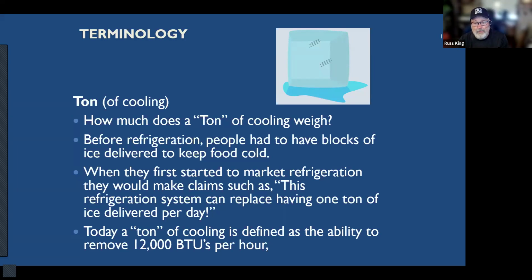All right, so 12,000 BTUs, 12,000 kitchen matches per hour, is its capacity to extract. So a 1 ton is 12,000, a 2 ton is 24,000, a 3 ton is 36,000 BTUs per hour. So when the manufacturers design an air conditioner, they shoot for one of those increments. They've designed enough of them that they know how big to make things for it to be right about 12,000 or 24,000 BTUs per hour. But then they send it off to a laboratory to have it tested, and that testing agency sends back the exact capacity of that air conditioner, and it's never exactly 12,000. It's right around 12,000 BTUs per ton, but they will call it their 2-ton system or their 3-ton system.